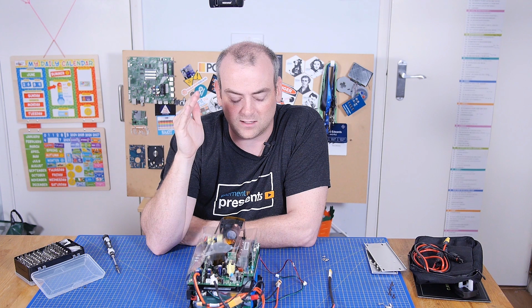Absolutely fine. The trouble is that conversion process is pretty efficient, 90-95% efficient. But I've installed UPSs that are 160 kVA, 160 kilowatts, in pairs to make sure that if one needs maintenance, the other one could go on. And bigger, 250 kVA - they're not uncommon for buildings with data centers and things like that. When you get to full-scale data centers only, not just like a data room in a building, these things get bigger and bigger, and you can imagine losing 5 to 10% of that is quite significant. In that case, if you think your equipment is fault tolerant enough, you may consider, rather than using a double conversion UPS, what I think are called online standby UPSs.